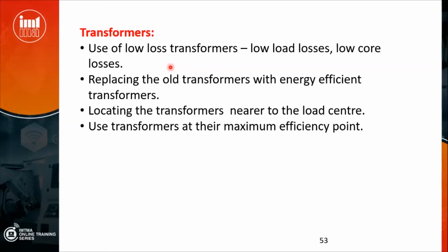Similarly, when you are seeking a transformer for your industry, at what load it should operate and what the efficiency of that transformer is, please have a discussion with the supplier. It can give perhaps a 10% increase in efficiency. Normally industry load will work at higher loads. At that particular percentage load, your transformer should give a better efficiency. That point you must make with the supplier.